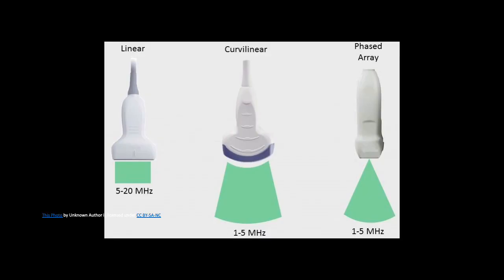So each probe has a footprint or a beam configuration. It has a frequency range. High frequency, short wavelengths, or more cycles per second are better at resolving smaller structures, but they can't penetrate as deep. Low frequency, longer wavelengths, less cycles per second, but better at penetration, depth, and distance.